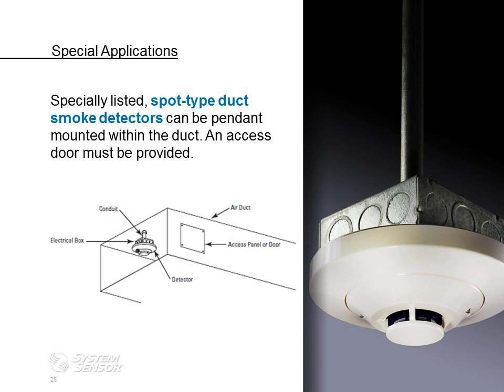There are some special applications that we run into. These detectors, while not a true duct detector, are still a smoke detector that's mounted in duct work. They're specially listed for pendant mount applications. It's a spot type duct smoke detector for pendant mount in duct work. And these are applied in spaces where there's either space constraints or we have to meet a no flow or low flow airspeed application. If you're less than 100 feet per minute of airflow, that's considered no flow, and then we would have to use a spot type detector versus a duct detector.